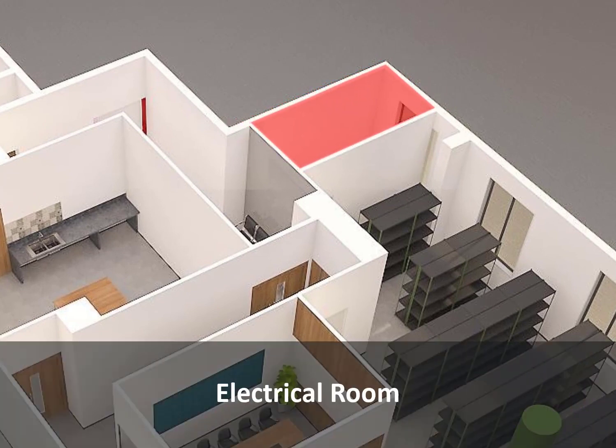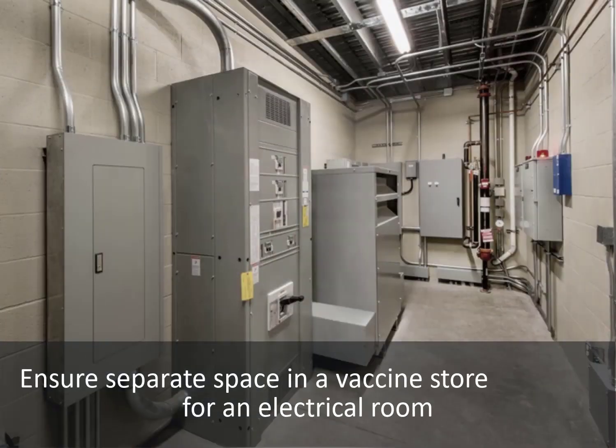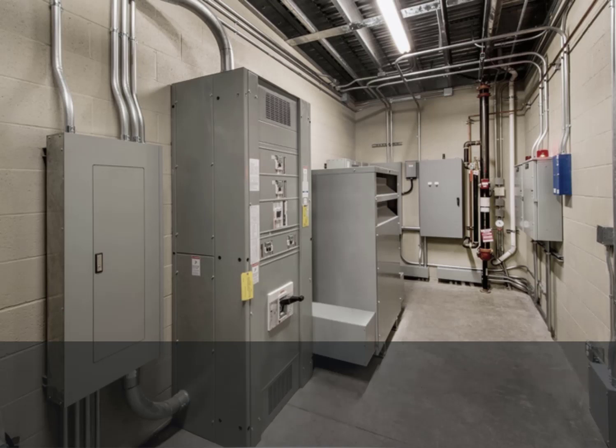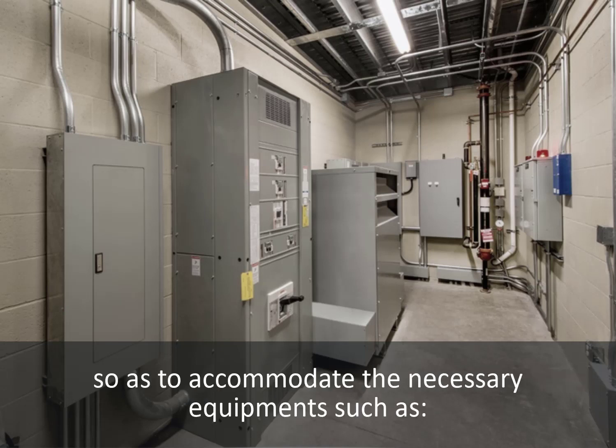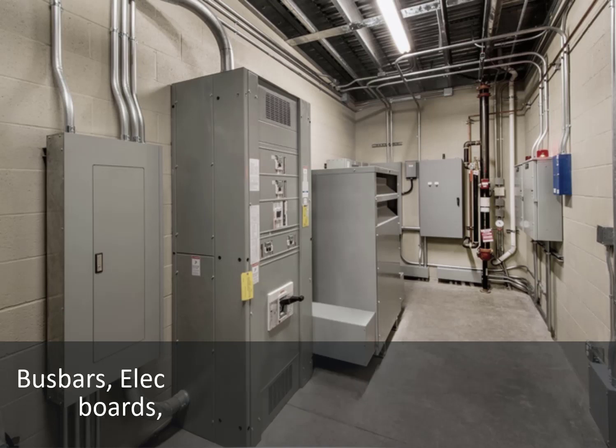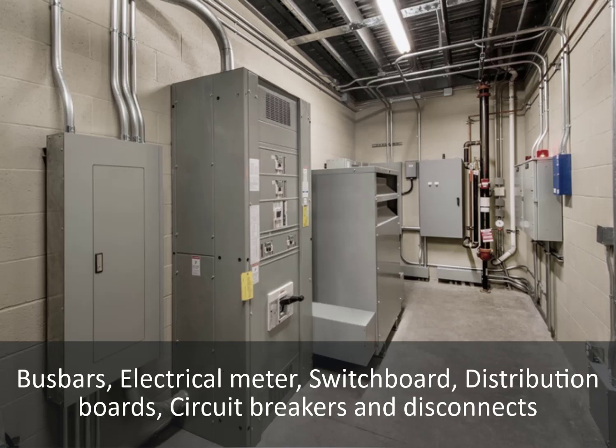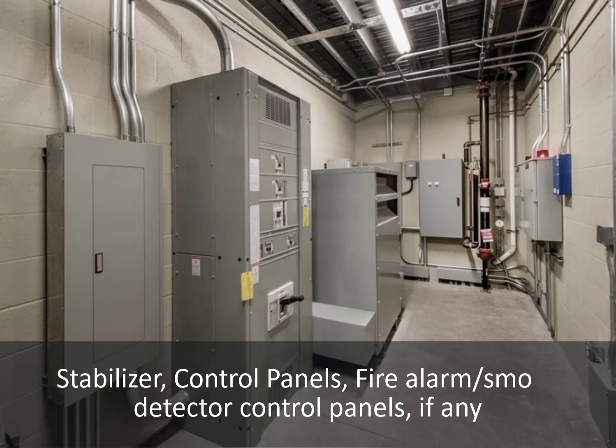The electrical room. Ensure a separate space in the vaccine store building for an electrical room so as to accommodate necessary equipment such as bus bars, electrical meter, switchboard, distribution boards, circuit breakers and disconnects, stabilizer, control panels, and fire alarm or smoke detector control panels if any.